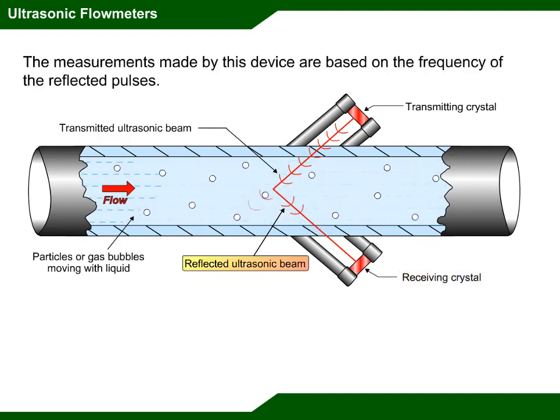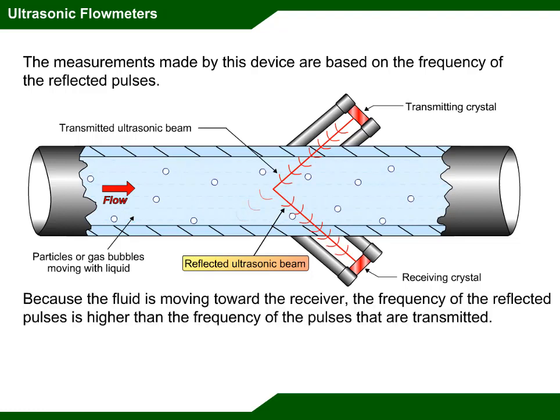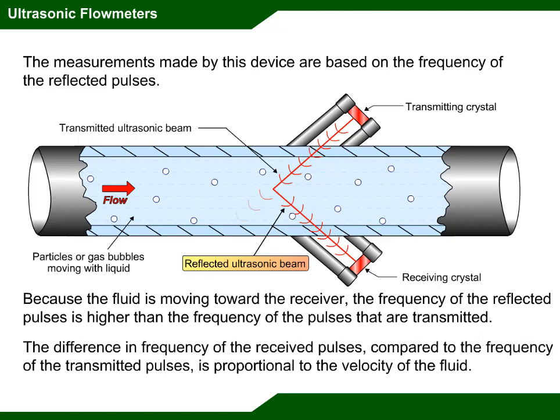This transducer converts the sound into electronic pulses that are processed by the sensor's electronics. The measurements made by this device are based on the frequency of the reflected pulses. The difference in frequency of the received pulses compared to the frequency of the transmitted pulses is proportional to the velocity of the fluid.